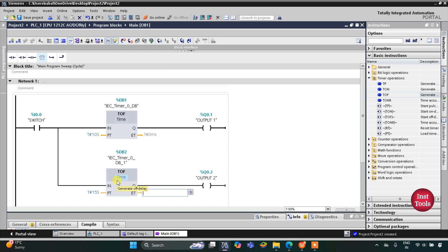When the switch is turned on, output 1 and output 2 both turn on immediately. When the switch is turned off, the outputs will not turn off immediately because we have used TOF timer operations. The TOF timer introduces a delay of 10 seconds before turning off output 1, and after 10 seconds output 1 will turn off.